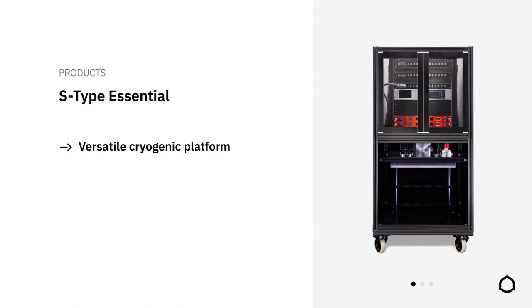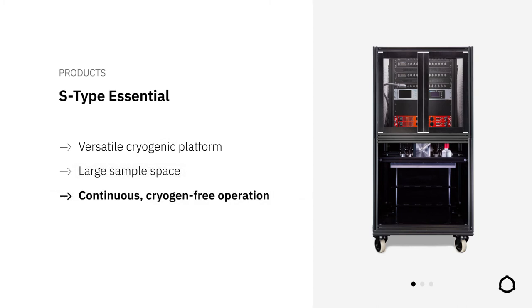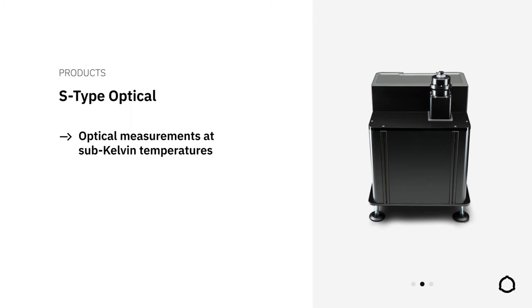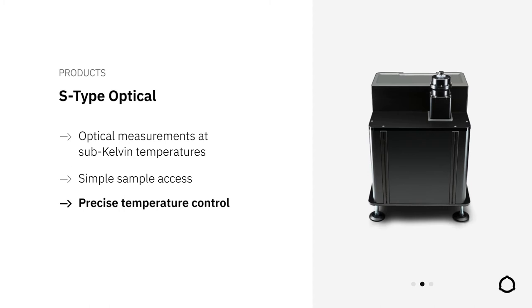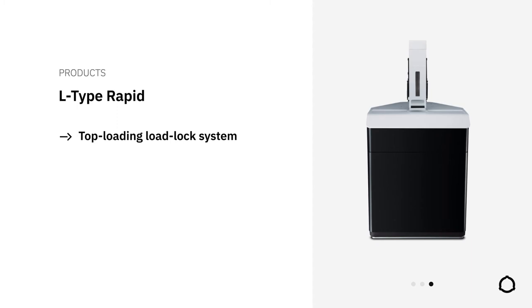First, the S-Type Essential, a versatile and ultra-compact sub-Kelvin system that offers a large sample space for complex customer setups and can serve as a platform for the continuous operation of quantum detectors. Second, the S-Type Optical, a compact sub-Kelvin cryostat derived from the S-Type Essential. It offers free beam optical access and an easily accessible sample stage as well as ultra-precise temperature control. Third, our L-Type Rapid, a fast characterization tool offering top-loading of samples, continuous operation down to 300 mK and one-shot operation to 100 mK with sample cooldown times of less than 3 hours.